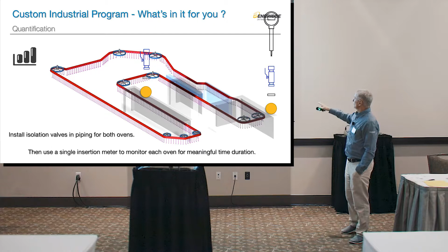The other thing I like about insertion meters is flexibility in installation. Remember those isolation valves? Say you have a paint line with a dry-off oven and a bake oven, so two pipelines going into each oven. You can put isolation valves on both for about $1,200 each. Then when you're ready, you put the insertion meter in one, keep it there a couple of weeks, see how the line runs, get a sense of how much energy it's using, then take it out and put it on the other. You don't need to pay for two meters.